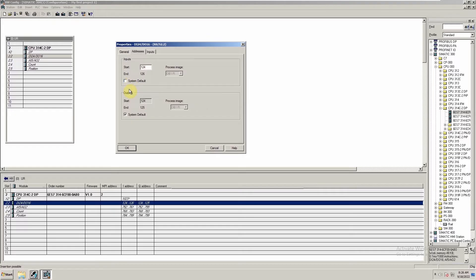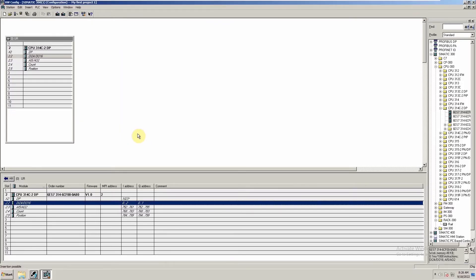Right now these are system default addresses, assigned automatically by SIMATIC Manager. If you want to change these addresses, you can do so. First, uncheck the system default option, and then you can change the input addresses — for example, put zero here. The same way, we can change the output addresses to start from zero as well. We click OK, and as you can see, both I and Q addresses have been changed and are now starting from zero.